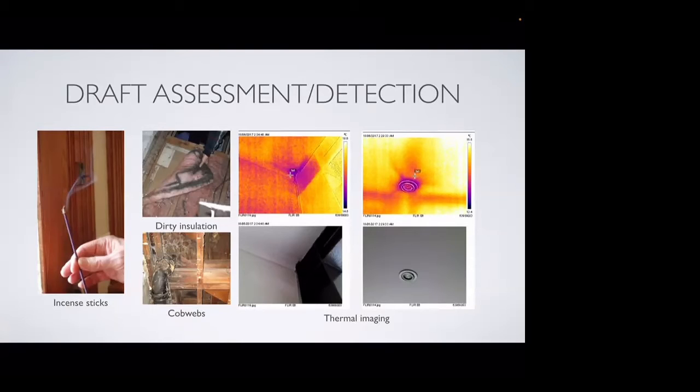In the photographs you see here, there's a leak in the corner of the ceiling, and it's in purple. And then, of course, you see a lot of air loss through the downlight there, or I think even heat gain is in the photograph. That's heat loss, actually, yes. It's a very cold spot. That's because I think that downlight is a gimbal downlight, and that has air gaps around the light, letting all the heat out and the cold in.